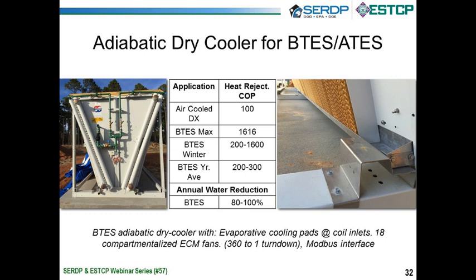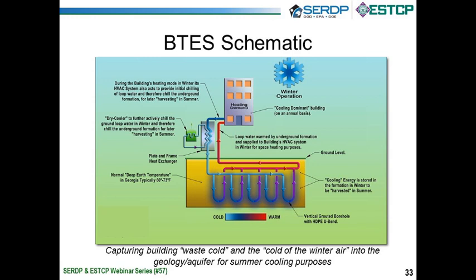So obviously, when it's cold outside, you can reject heat more efficiently than you could in the summertime, and also you can do it without evaporating water. Evaporating water is kind of a crutch we engineers lean on, so we can get an 85 degree heat sink instead of a 95 or 100. And it's not a bad crutch if you've got plenty of water. I'm not against evaporative cooling, but we do have a guest with us from South Africa, and very interestingly, the Green Star program they adopted instead of LEED penalizes you if you use water to evaporatively cool. That's starting to get more attention here in the U.S., but in the projects we've done in South Africa, obviously the water there is pretty critical, and so they do recognize that evaporative cooling in and of itself has an environmental impact.